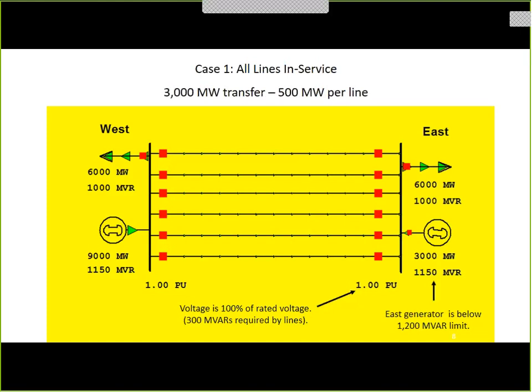Here's an example of that. I have the west and the east. This is kind of like a demo that we did for the blackout. This is a generator maybe in the western part of the eastern grid, which would be Iowa, Kansas, all those people. And the east is New York City and Florida, all those combined. And I show 6 transmission lines. The little red boxes are circuit breakers. The circles are generators. And the arrows are the loads. And if you look at the numbers, the loads are the same in both cases, totaling 12,000 megawatts. But look, the one on the west is 9,000. The one on the east is 3,000.